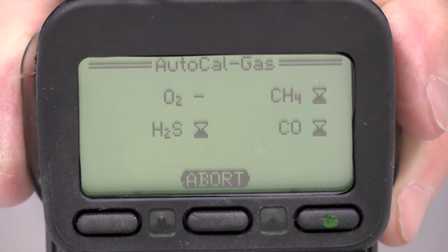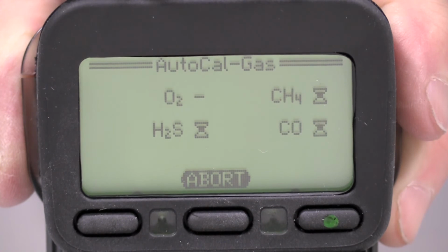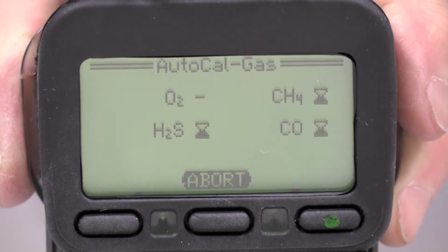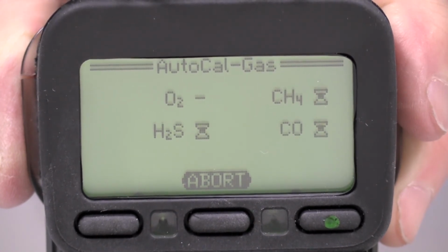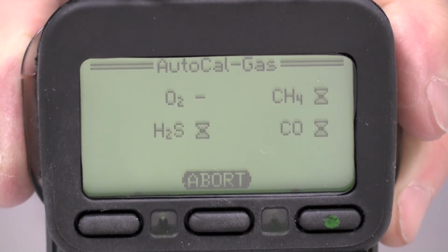The instrument will show an hourglass while each sensor is being adjusted, then a check mark when the adjustment is complete. At the end of the adjustment procedure, the display will show the autocal report screen. Turn the regulator back to the off position. Remove the calibration adapter from the instrument. An OK icon indicates that the sensor has been successfully adjusted. An error message indicates that the sensor was not successfully adjusted.